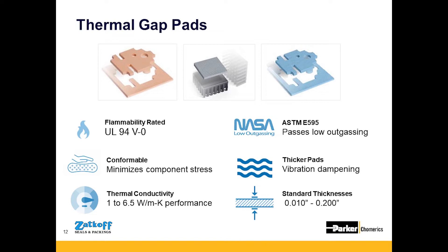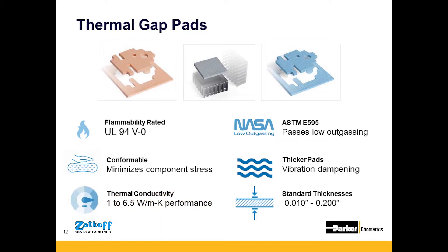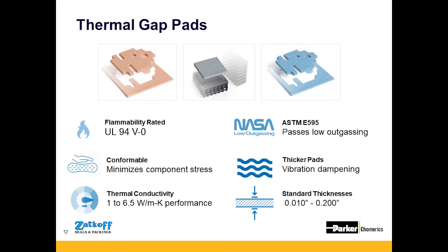Gap pads are offered in a wide range of sizes and thermal performance. From a size perspective, they range from small custom die-cut parts based on customer drawings to sheet format — either 18x18 inch sheets or up to 20x25 inch sheets. Thermally, the material is offered from 1 to 6.5 watts per meter Kelvin. Thicknesses range from 10 thousandths of an inch up to 200 thousandths, and for some applications we can go up to half an inch thickness. They are also offered with a variety of different carriers.